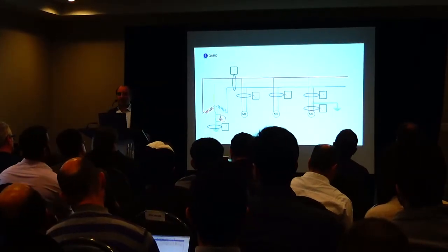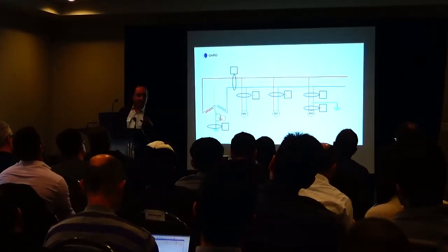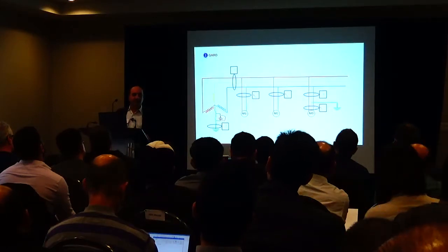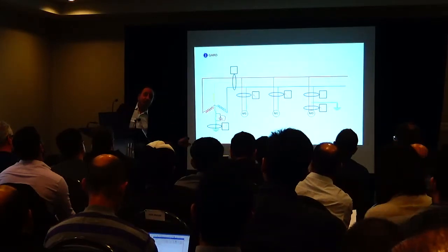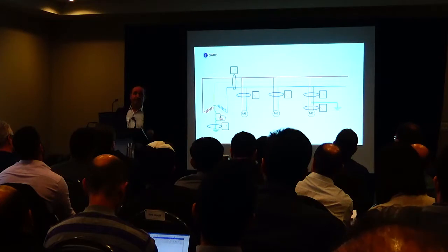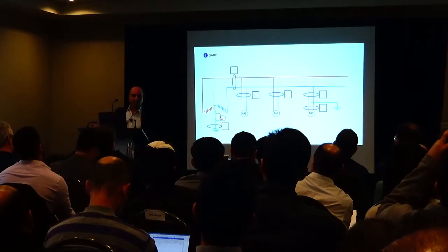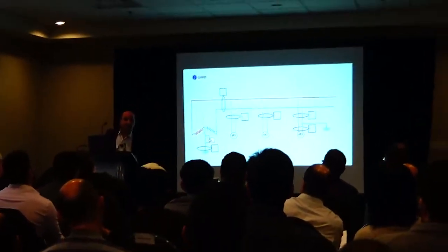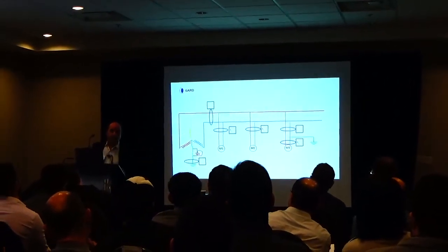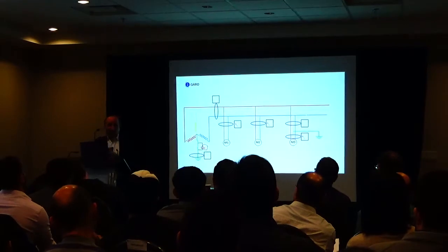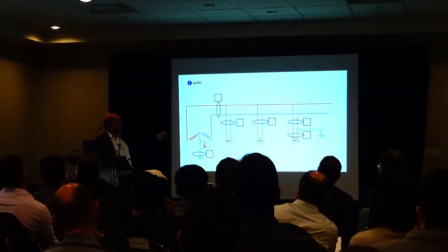So you can find the fault very easily, in less than 1 hour in any size facility. The capability is there to locate where the fault is. The willingness may not be there. And what's the cost? You remove the G element on the breaker with this sensor. You want to look at cost now. So let's look at this.